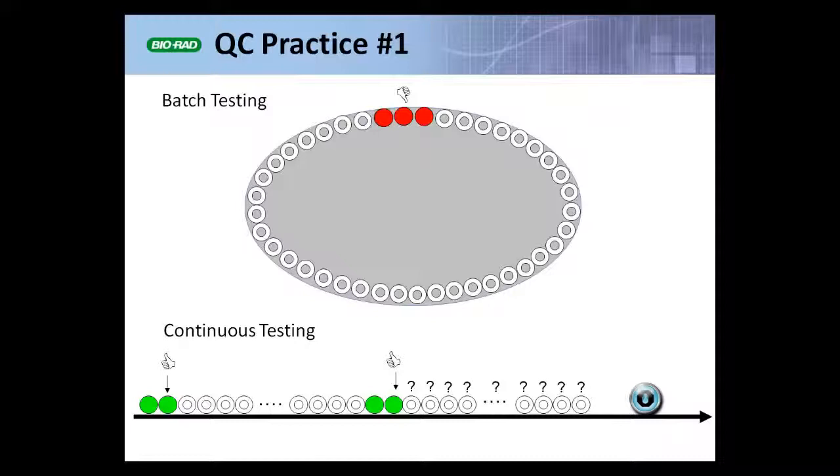Or maybe I've reached a point where I'm going to do preventive maintenance or a scheduled calibration—some event that might change the state of my testing process. If I don't test quality control specimens after the last patient result but before that stopping point, then I can't guarantee that something hasn't gone wrong that's adversely affected all the patient results produced since the last acceptable QC event.